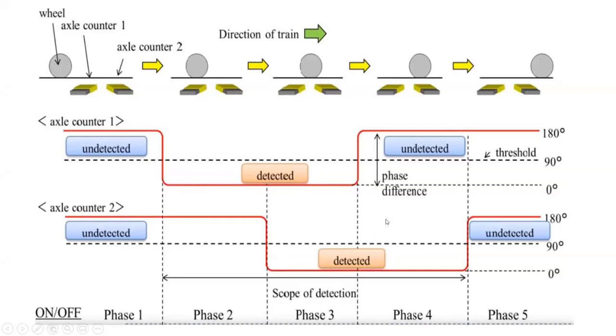This is phase three. And then phase four, the sensor one has picked up, the receiver voltage has gone up, and a little later, sensor two. So like this, there are five phases. Phase one and phase five are the same, and in between, there are three phases. All these pulses are processed by the pulse detector and given to the processors.